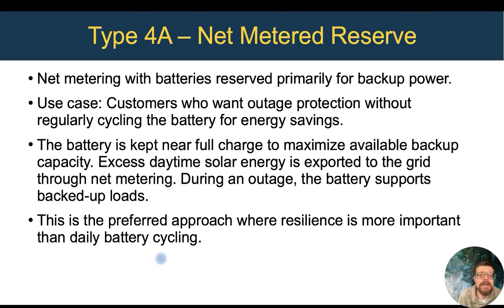Net metering is what we used to have a lot of and we're having fewer of now, but there's still a fair amount of places with net metering. And this first type, 4A, is what we always used to call net metered PV with grid tie with battery backup. Keep the batteries full all the time in case you have a power outage, and you just cover your loads and then sell any extra solar during the day. We do want to cycle the batteries just a little bit, maybe down to 95% each day, just because there are some issues if you keep them at 100% all the time with the BMS calibration and such. But generally, you're keeping the batteries just about full all the time and just selling power. So that's a fairly simple setup.